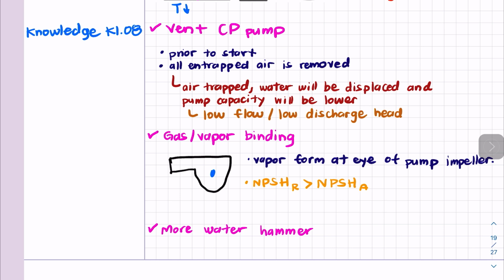One common method of venting is a vent valve or vent plug located at the highest point in the pump and suction piping. This allows air to escape as liquid enters the pump and fills the system. Another method is to use a priming pump or other device to force air out of the system and prime the pump. That's what it means when they say prime the pump.